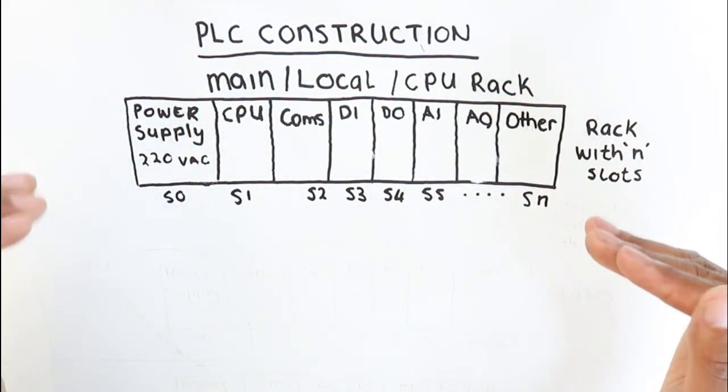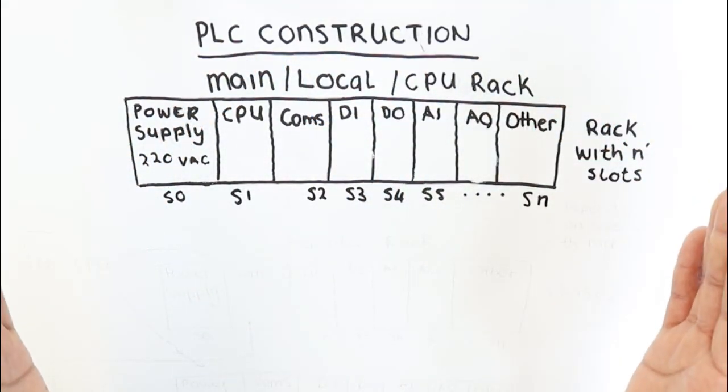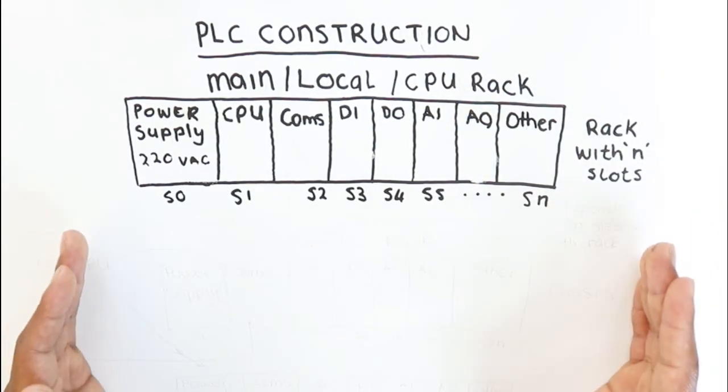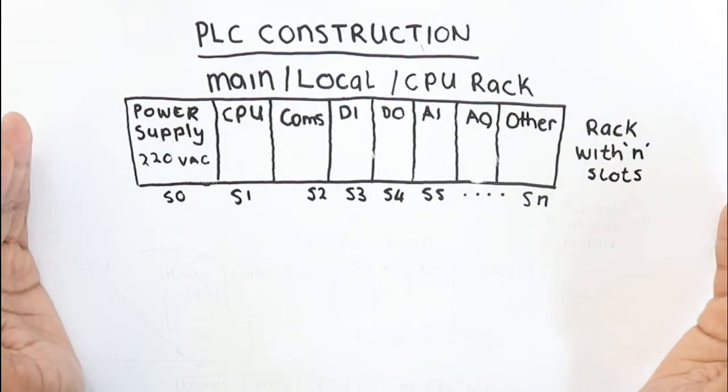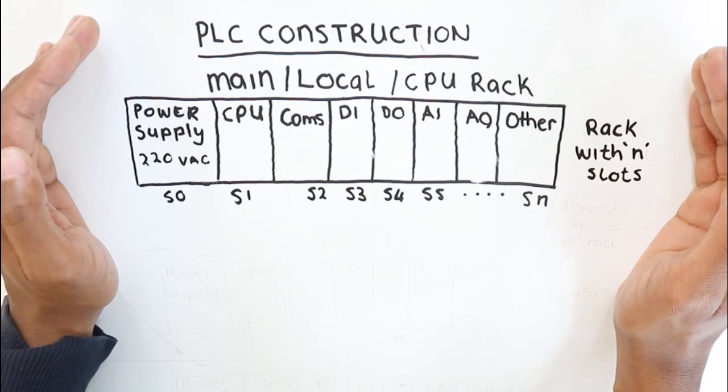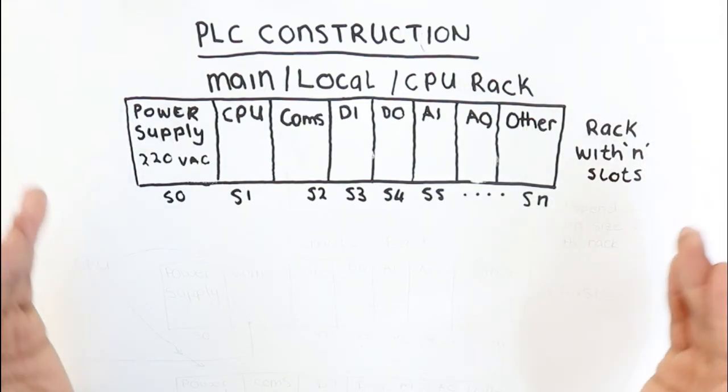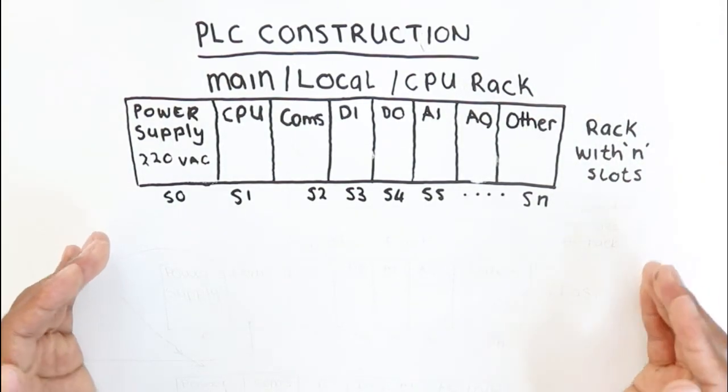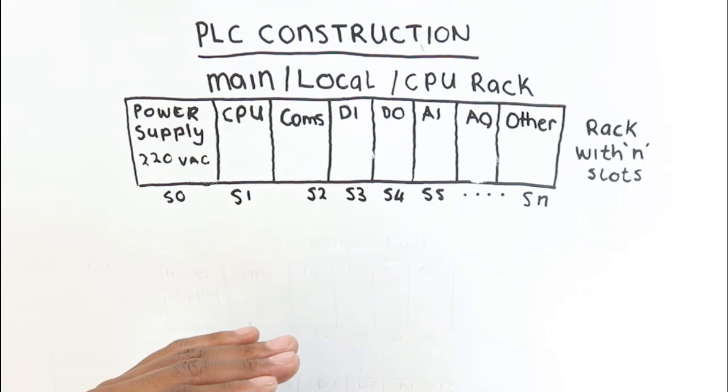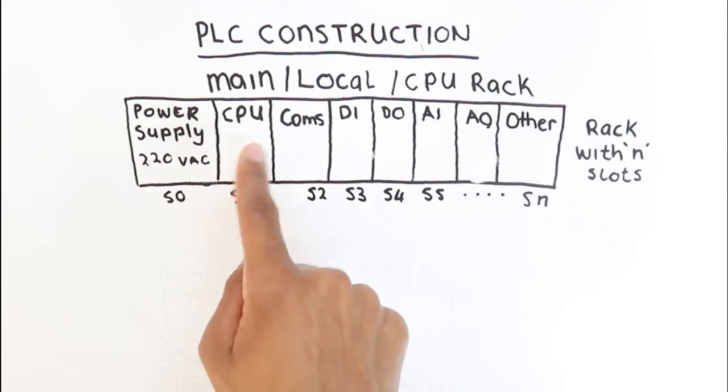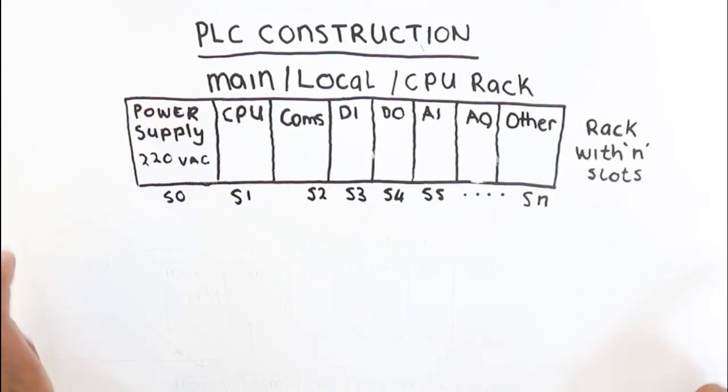Now the fact that there is something called a main rack means that we also have another type of rack in our PLC construction, and that is called the remote rack. Why is that necessary? You'd need remote racks because if you run out of space on your main rack, you need to have your IO being interfaced with the PLC on another rack. That remote rack must then be able to transfer the signals to and from the CPU.